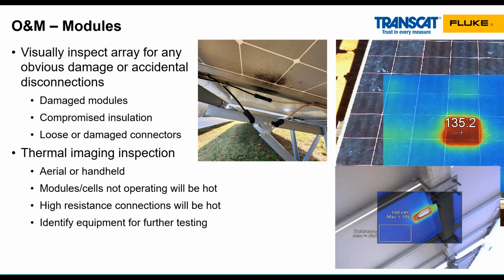With thermal imaging of modules, the parts of the module or array that are not operating will be at a higher temperature than operating components. That's because the electrons in the cell are being excited by the sun, and if they don't have a load, they don't have anywhere to expend that energy, so they will dissipate some of that energy as heat. Connections that are high resistance, like module interconnections that weren't plugged in all the way, will be hotter than other similar components under similar conditions. And many times with thermal imaging, we're not necessarily diagnosing what the issue is, but we're identifying problems that need further testing to find out what the root cause of the problem is.